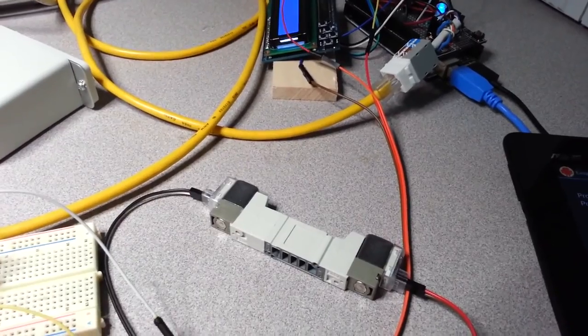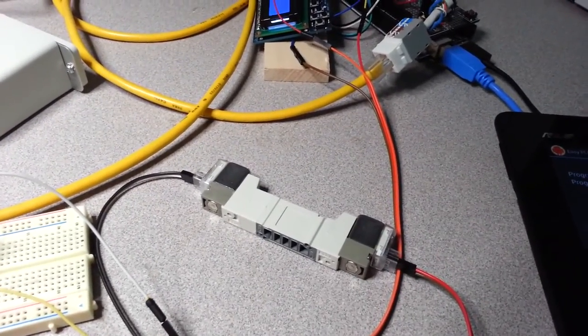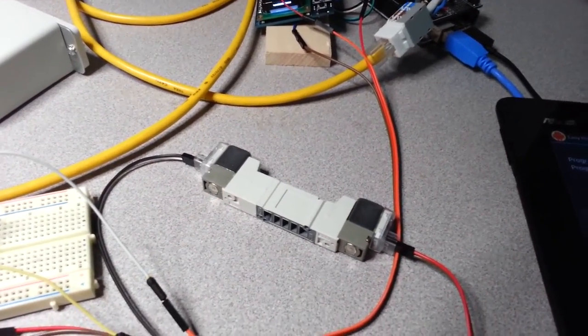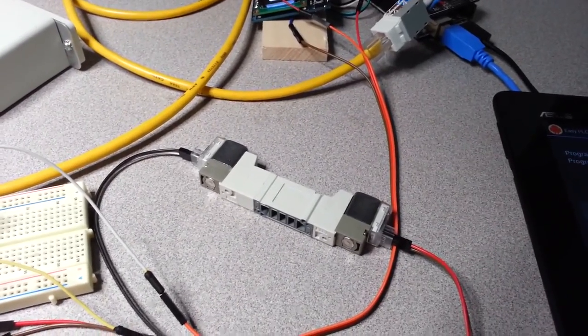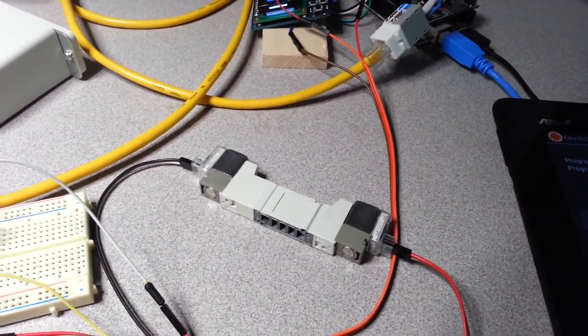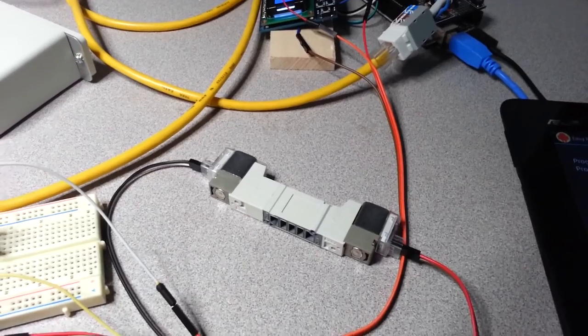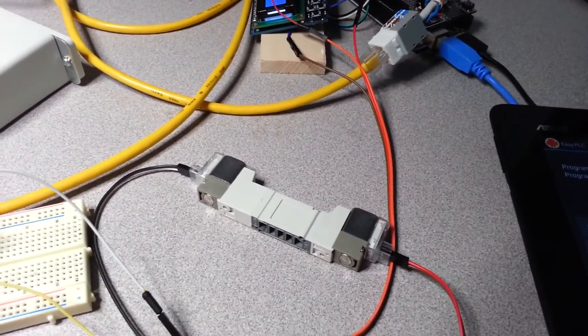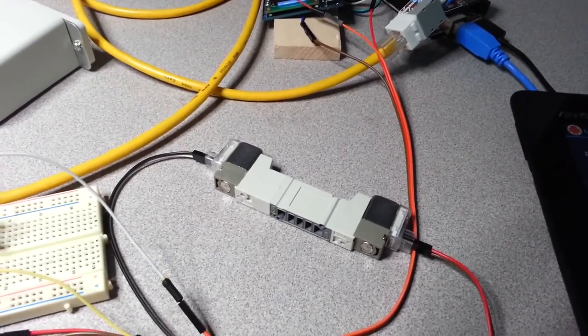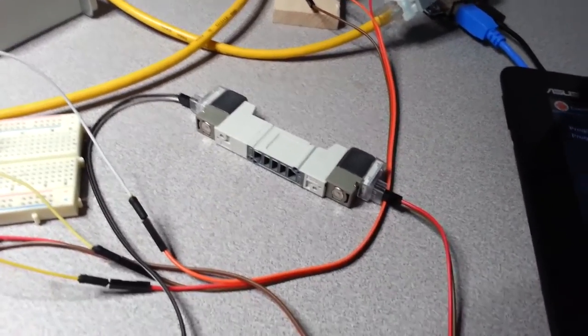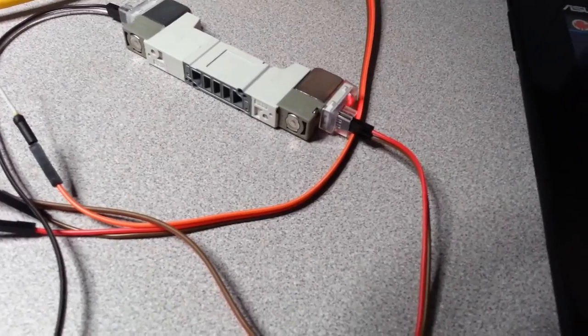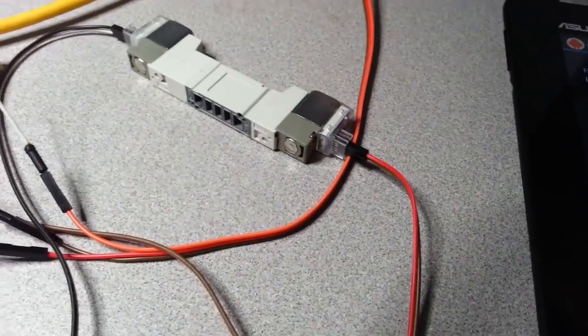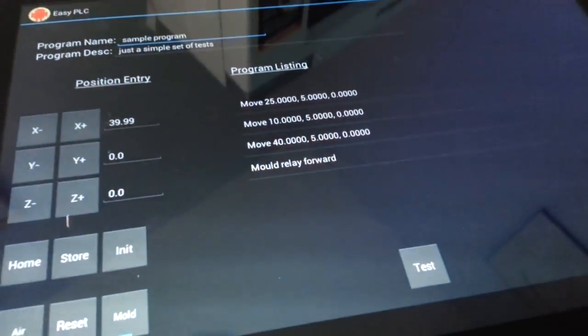If it doesn't, it shuts things down and forces you into an error condition because either the airline isn't working, something's jammed—who knows what—it's just an error condition. So I'm going to fire off this mold. You can see the LED came on, and then when I press the end stop button here, the light went off and it's stored that in the program: relay forward.